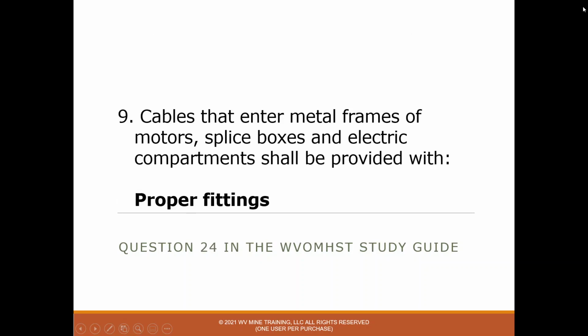Number 9, cables that enter metal frames of motors, splice boxes, and electrical compartment shall be provided with, and that's proper fittings. So anytime a cable enters a box, if you could just imagine we have this metal enclosure, so we cut a hole in it to get a cable into it. We know it could have sharp edges on it, so we have to protect that cable with proper fittings. And if it is a permissible enclosure, then it would have to have a permissible fitting or entrance gland into the box.